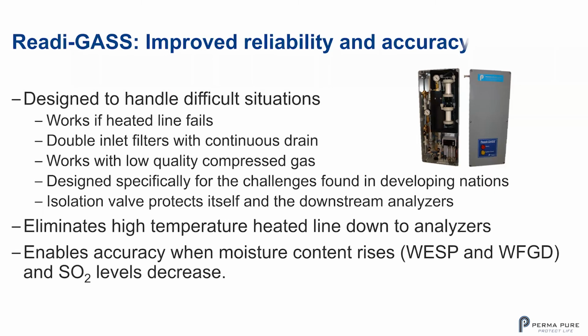The Readi-GASS is designed for improved reliability and accuracy, designed to handle difficult situations. It works if your heated line fails. We have double inlet filters with a continuous drain. It works with low quality compressed gas, and it's designed specifically for the challenges found in developing nations. The isolation valve protects itself and the downstream analyzers. It eliminates the high temperature heated line down to the analyzers and enables accuracy when moisture content rises and SO2 levels decrease. It's a very good system for those applications. You could see inside we have dual coalescing filters. It's really designed for these difficult applications.